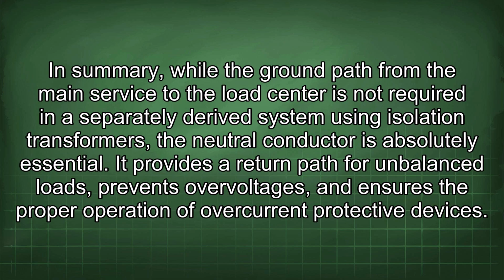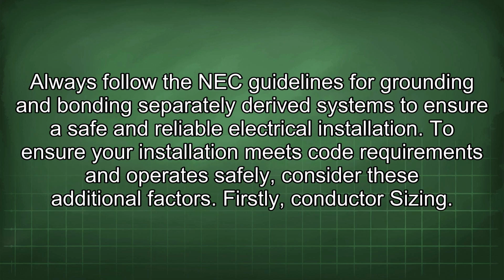In summary, while the ground path from the main service to the load center is not required in a separately derived system using isolation transformers, the neutral conductor is absolutely essential. It provides a return path for unbalanced loads, prevents overvoltages, and ensures the proper operation of overcurrent protective devices. Always follow the NEC guidelines for grounding and bonding separately derived systems to ensure a safe and reliable electrical installation.